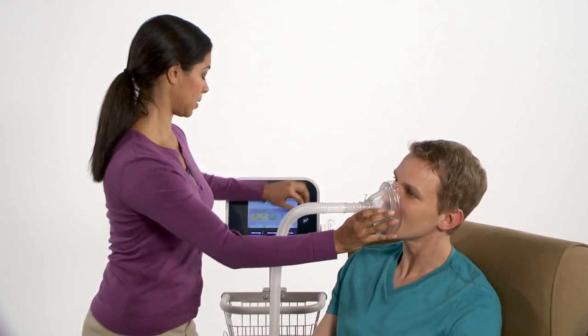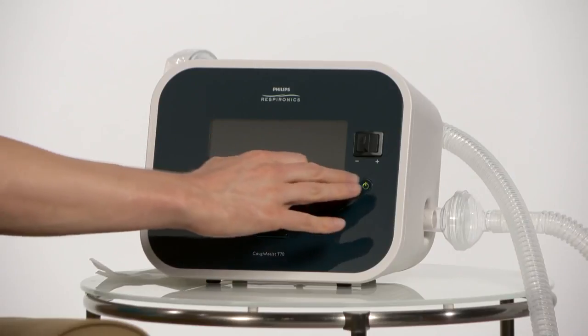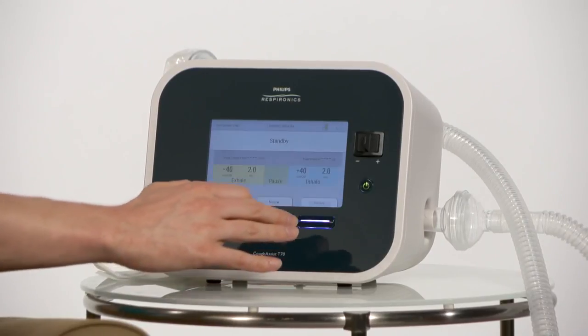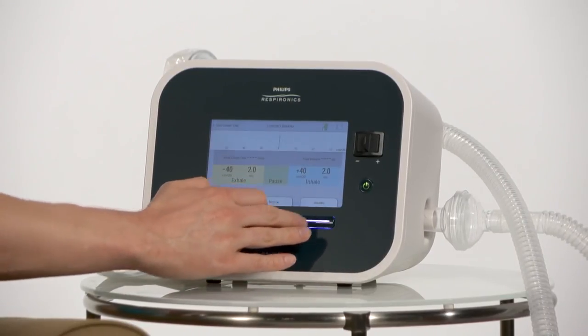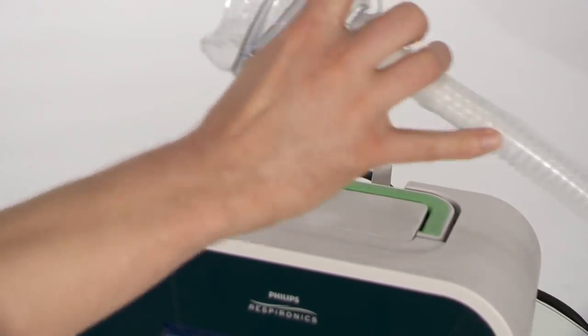When the treatment is finished, press the right button to halt the airflow and return to standby. The patient's prescription will determine how many treatments are to be administered each day, for example, a treatment every four hours. If the doctor orders the treatment as needed, the patient can determine how many treatments he receives during the day, depending on how often he needs to clear secretions.